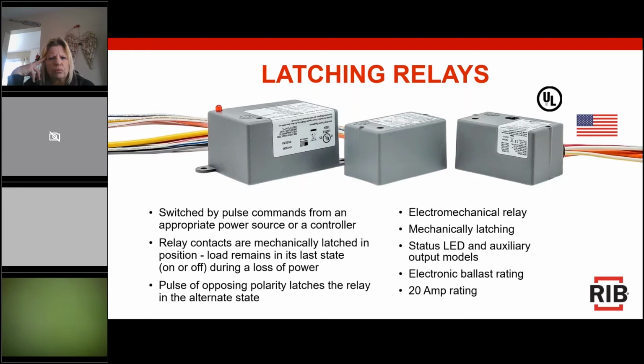Next, we have some of our specialty relays. We've got a series of latching relays. These are 20 amp rated relays, and they are switched by a command from either a controller or some other power source. Should the load lose its power, this allows it to remain in its last state, because the relay contacts mechanically latch in position. Again, just like all of our other relays, you've got your LED, and we've got some auxiliary output models.